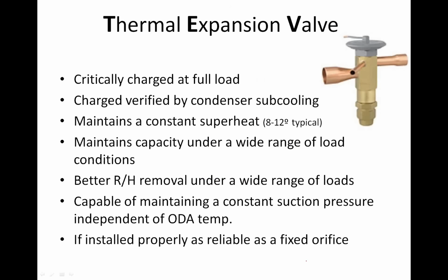Well, if we get this thing set up right, it maintains the constant, and I should actually add in the word in there, evaporator superheat of 8 to 12 degrees. There's two types of superheat in the system. There's evaporator superheat and there's total superheat. Evaporator superheat is the superheat that would be measured right at the evaporator outlet that the TXV is controlling.